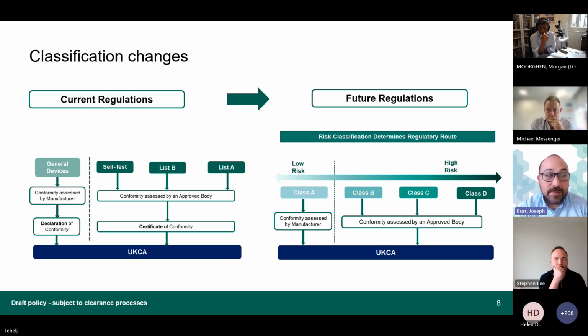marking on that device. Many devices these days actually are general class devices in the current regulations. They do not require a UK approved body, but you can self-declare against the essential requirements and the regulations of today. And then you can declare that through a self-declaration statement, and then you would place the UKCA mark to then allow you to register that with the MHRA. We're going to change that.